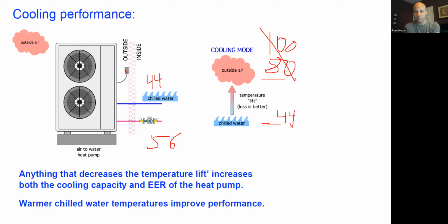And just like before, we can't control the outdoor temp, obviously. So that means instead of designing for 44 degrees, if I can design this for 46-degree water, meaning my air handler coils are just a little bit bigger, that might be beneficial to me. I can't get too crazy with it like I did with the hot water. Remember on hot water, we said we're designing for 180, but if you could design it for like 120, 110, that's awesome, by putting in big radiators and big coils.